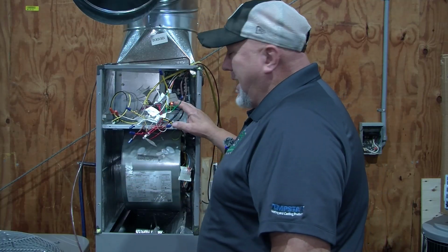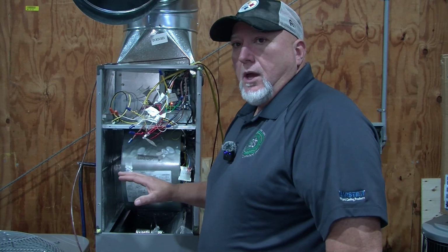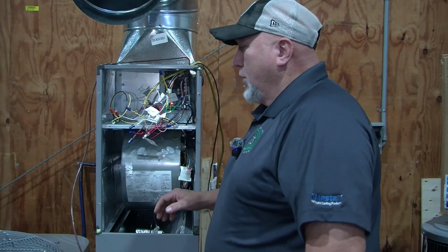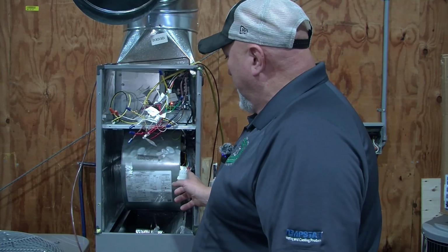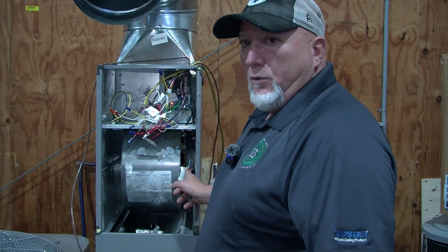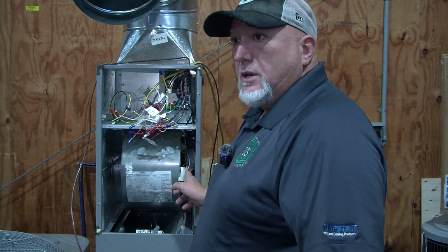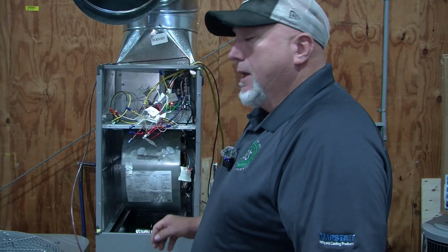If the amber light is on and the blower motor's running, but you don't have a call for AC to come on, then it is sensing there's a leak somewhere, or there's something that's not right with the system. So then you have to look, and you can pull your speed tap wire here off, and if the blower motor stops, that's where the call's coming in. I'll demonstrate that here in just a second.